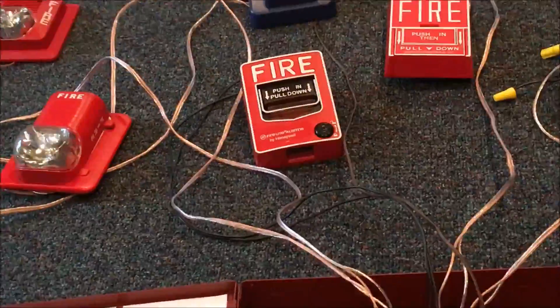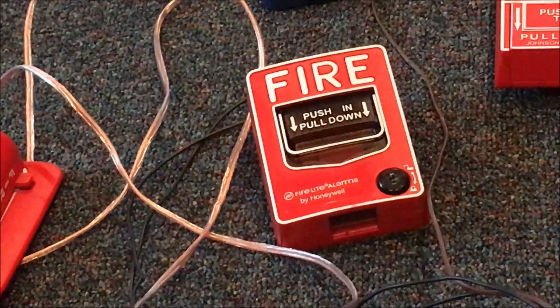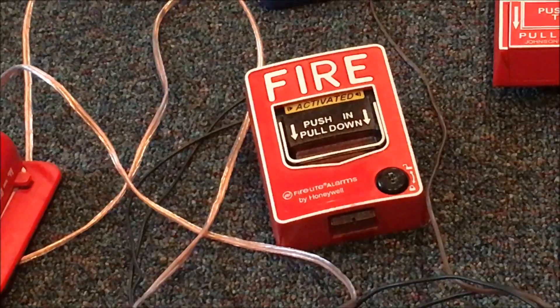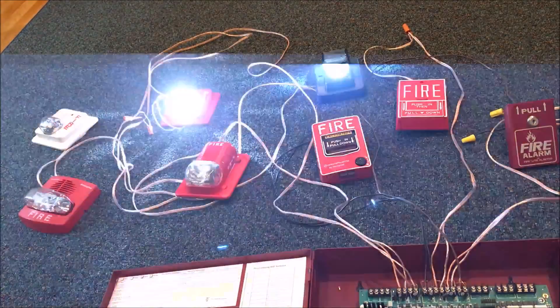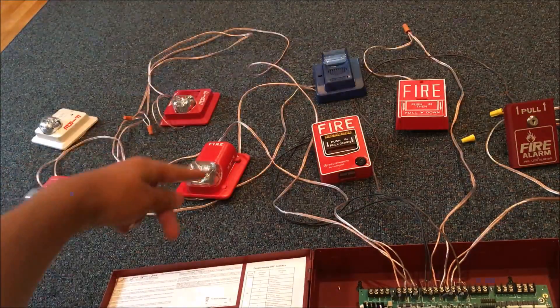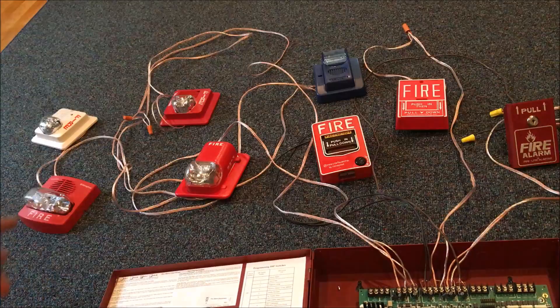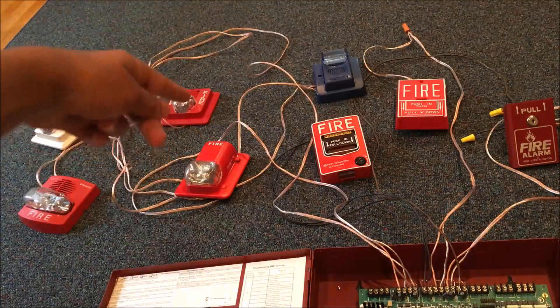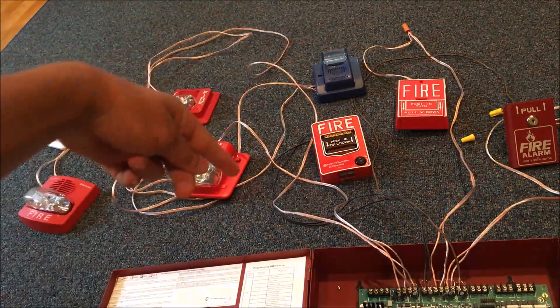So let's get to the test. Let's pull this one first. Let me put this back on here. Let's pull it — three, two, one. And as you can see, these three strobes right here are all in sync. This one flashes really fast, and that one flashes very slow. So these three alarms are all in sync.